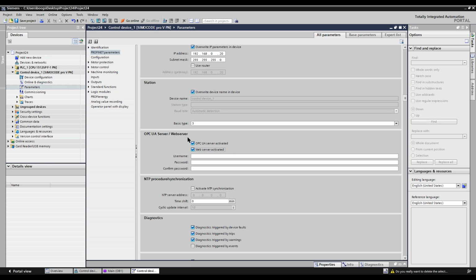And we'll talk about this. This is the connection to the cloud. This is where we would reach out to a historian and so forth. With the cloud is this OPC UA server. And then a web server is the means to be able to type in the IP address and look directly at the SIMOCODE and figure out what's going on with it without any software, without even plugging in. All you need is the IP address and be on the network with that SIMOCODE. And I'm going to demonstrate that in just a few minutes.